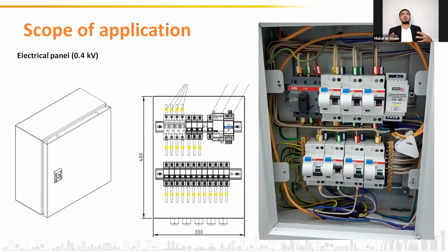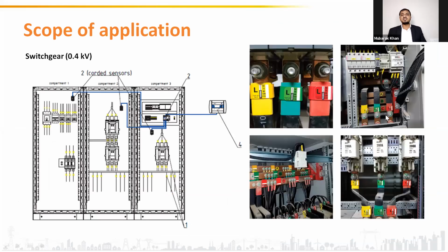Okay, now some photographs just for you to visualize how it will actually look inside a panel. In a small 440 volt, 220 volt distribution board, the stickers will be installed on the cable joints, and the FPA will be installed in the same compartment. This device which you can see here is the FPA. In an MCC, PCC type of panel where we have different compartments, sensors will be installed in each compartment. RFPTs will be installed on each joint, and it will be communicated to the remote PC through FPA. Now you can see here on the bus bars, these sensors are installed like this.